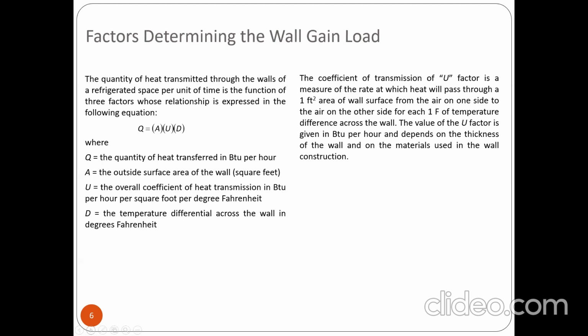So, factors determining the wall heat gain. Pag-compute. The quantity of heat transmitted through the walls of a refrigerated space per unit time is a function of three factors whose relationship is expressed in the following equation, where Q is equal to A, U, D. Q, quantity of heat transferred in BTU per hour. A, the outside surface area of the wall, square feet. U, the overall coefficient of heat transmission in BTU per hour per square foot per degree Fahrenheit. D, the temperature differential across the wall in degrees Fahrenheit.